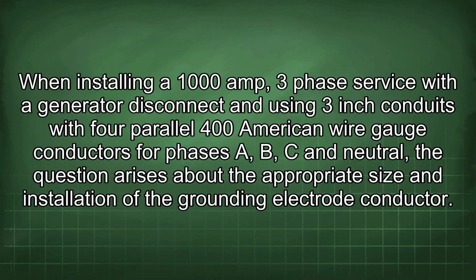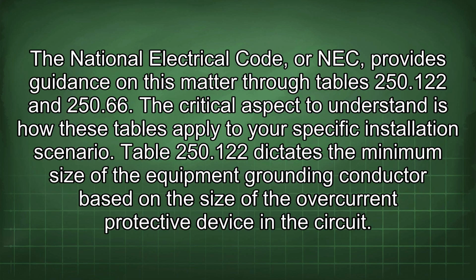When installing a 1000 amp 3-phase service with a generator disconnect and using 3-inch conduits with 4 parallel 400 American wire gauge conductors for phases A, B, C and neutral, the question arises about the appropriate size and installation of the grounding electrode conductor. The National Electrical Code, or NEC, provides guidance on this matter through tables 250.122 and 250.66. The critical aspect to understand is how these tables apply to your specific installation scenario.